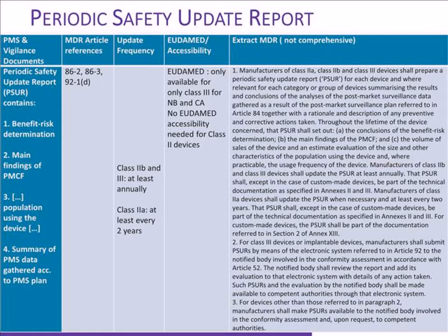We're going to an end with this report, so don't worry. This is the last one, which is the periodic safety update report, also known as PSUR. This report is required for class 3 and 2B to be updated at least annually, which is here as well a significant burden. It's also required for class 2A, where it needs to be updated every 2 years.